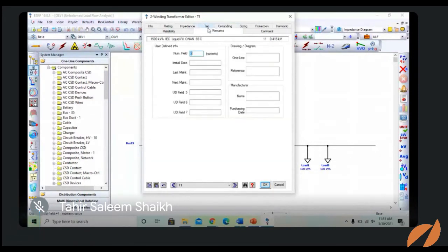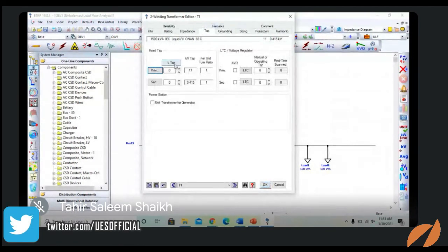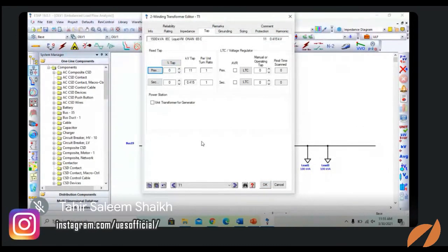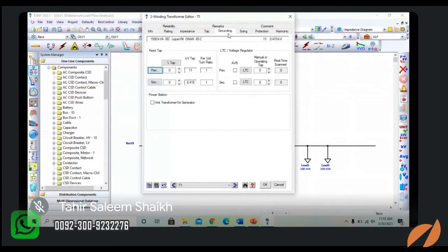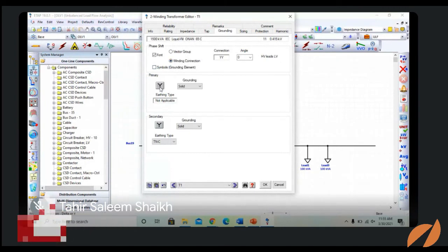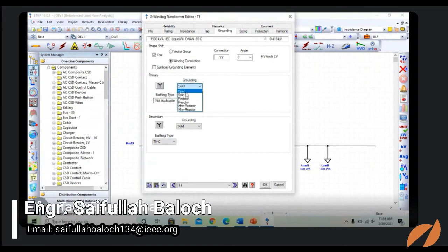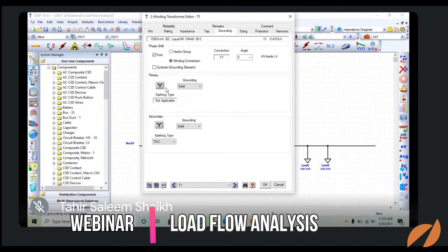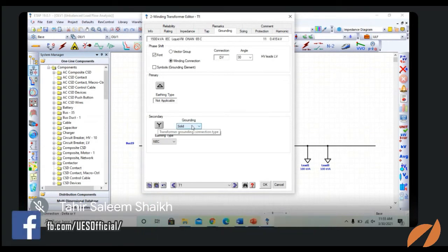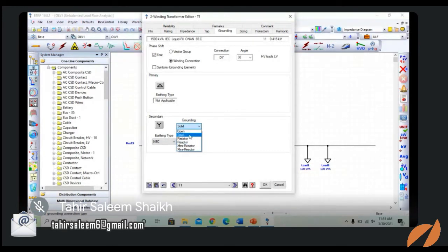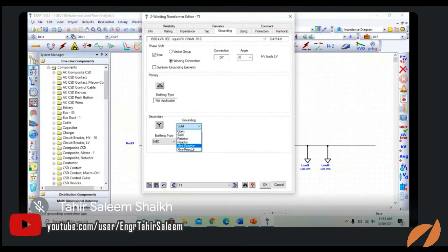Okay, now tap setting, what kind of percent tap, like in distribution transformers or power transformers, we have different tap settings. So you can also change this tap setting from here. What grounding you are using: if you are using a primary star, we have to select the grounding, either open or solid. But for the distribution transformer, we have a delta primary and a star secondary. So for the grounding, solid, and as you can see, we have different earthing: open, solid, resistor, reactor. But in these systems we are using solid earthing.